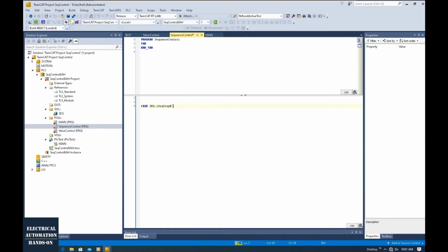After this, we need a CASE here. The system will automatically create this END_CASE. Within here, we will program the different numbers. For the first step, we can name it 0, and we can type in some comment here. Firstly, this number will be used for initial. At the initial step, the operator will load the housing into the machine. Once the part is present, after the palm out button is pressed, the machine will move to the next step. To program this structure, firstly I will program to show the current step description.